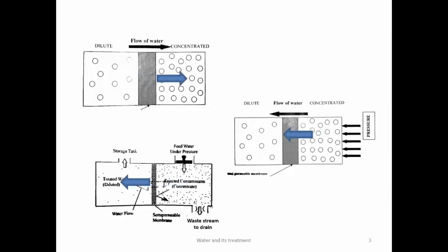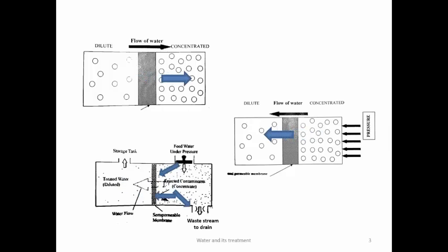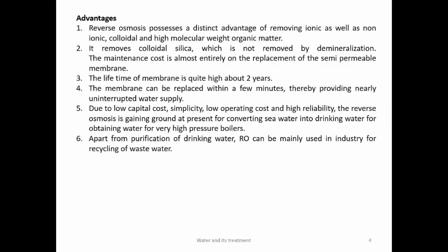After some time the semipermeable membrane gets blocked, so it is divided into two parts: one for purification and one for washing. Rejected contaminants are removed to drain as waste, and soft water is collected and passed to a storage tank. Advantages of RO: removes ionic and non-ionic colloidal high molecular weight organic matter; removes colloidal silica not removable by demineralization. Maintenance cost is mainly membrane replacement; membrane lifetime is around two years and can be replaced within minutes.